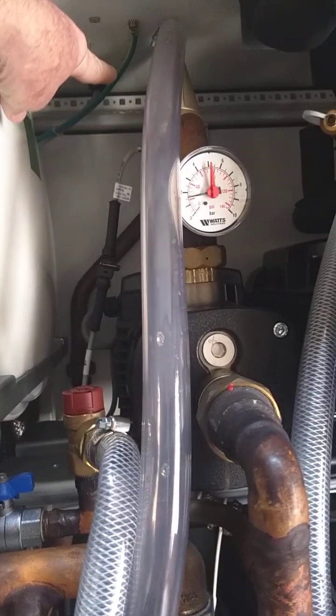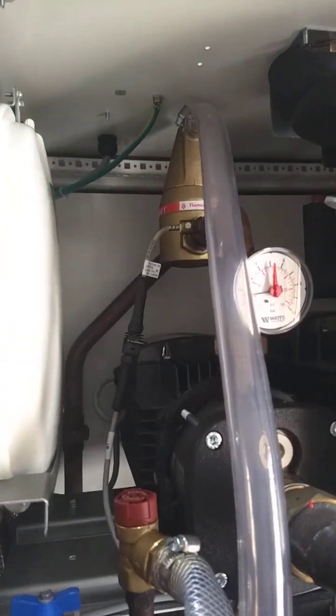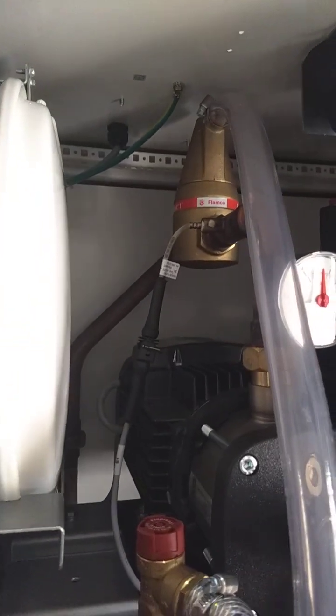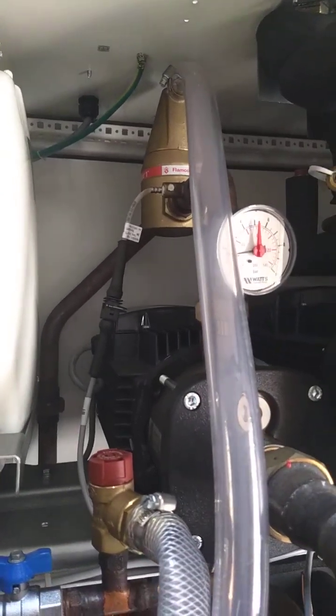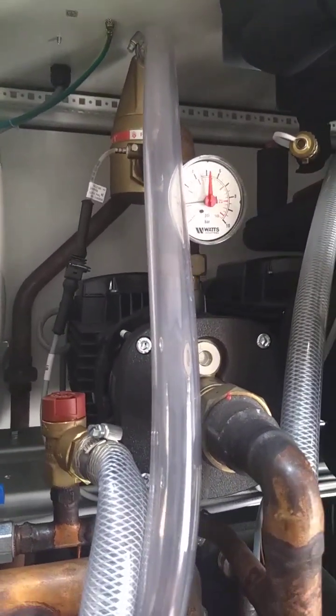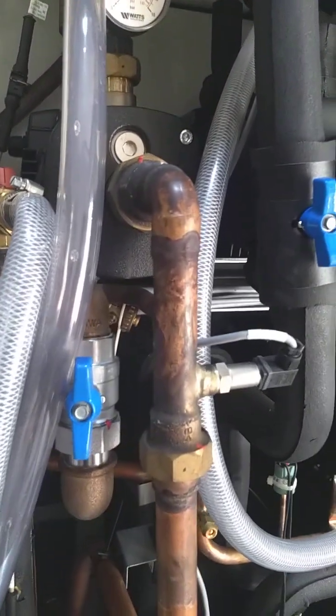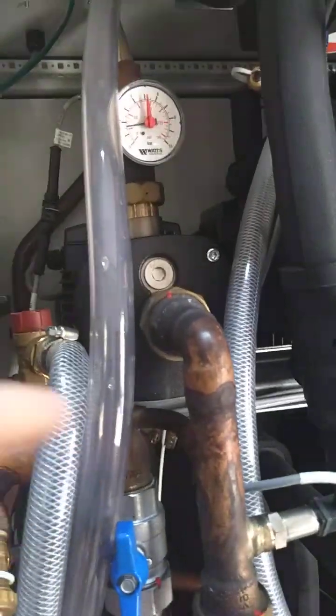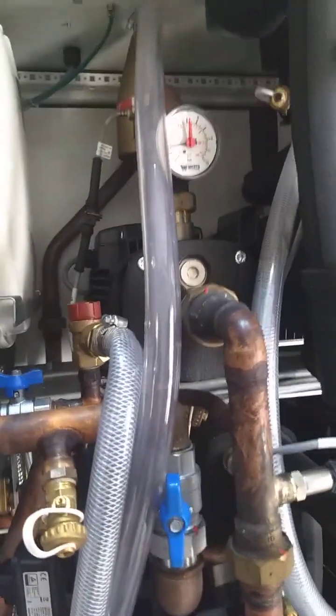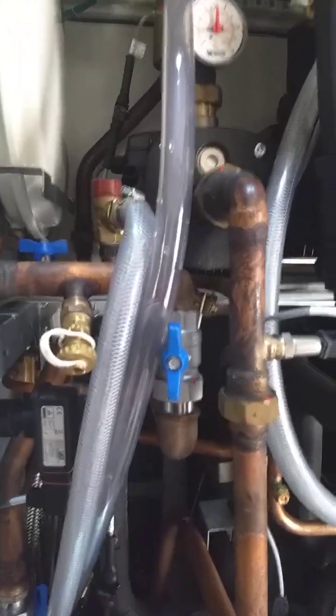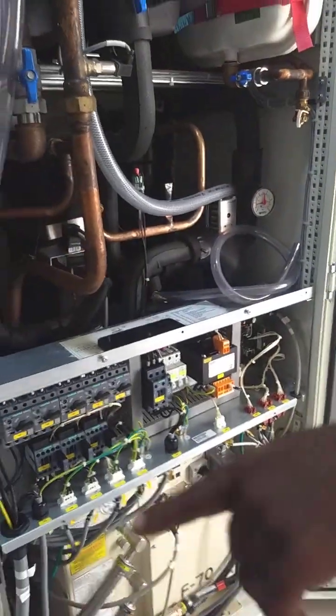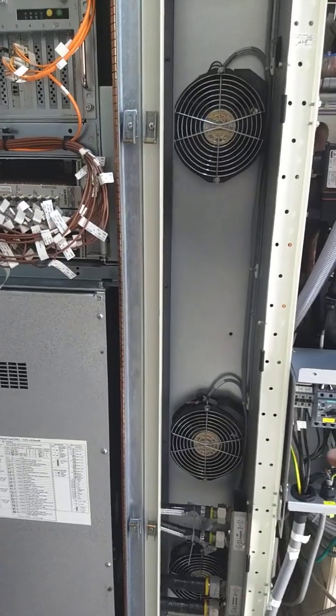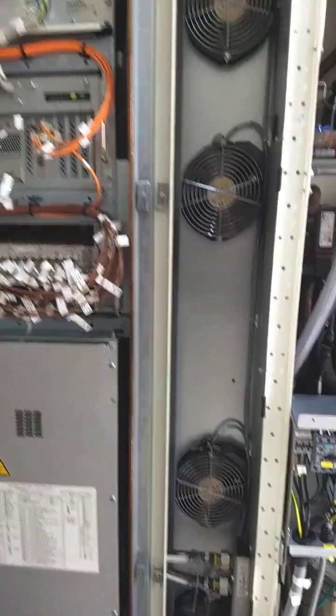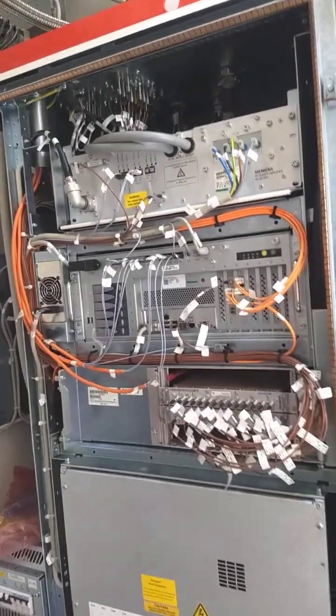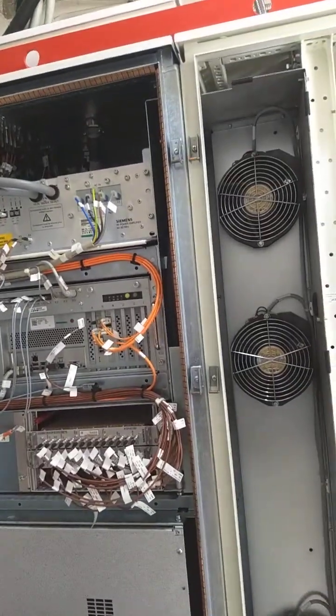And what is this unit here? That is a valve, called a solenoid valve. It's controlling the pressure and everything. And this is an overflow tube? Yeah, overflow. So this is secondary water. It's cooling the helium compressor. It's cooling the gradient power amplifier. It's cooling the radio frequency amplifier. It's cooling the gradient coil inside.